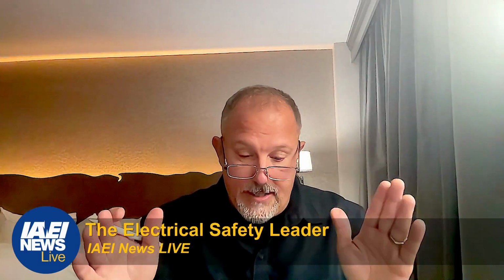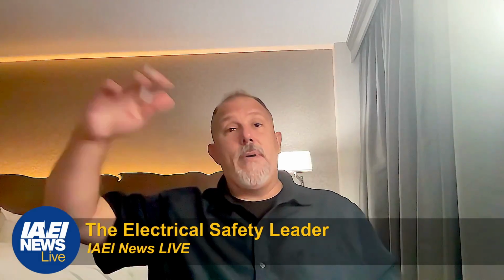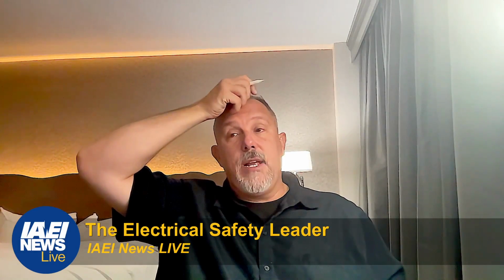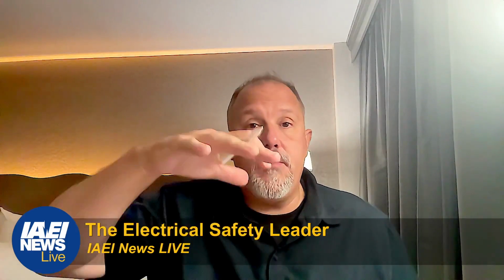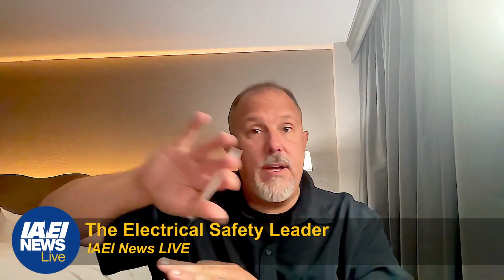So what we learned was that promoting that use of cords going over the edge created opportunities for children, elderly, and others to pull grease, deep fryers, etc., from the countertop on top of them. And we looked at the data, and I'll tell you what we did. We actually went back and forth. Some of the code panel members would say, look, let's make it required to have a receptacle on that peninsula or island, and we'll still use the calculation, but all the receptacles have to be in the top, like a pop-up, or two-tiered islands where you can have it on the face, but it can't be extending over. So we had that extreme, to one saying we should not permit a receptacle on an island or a peninsula based on the data that we saw.